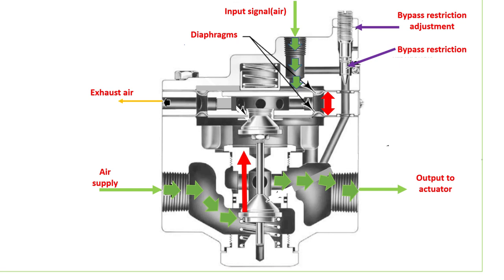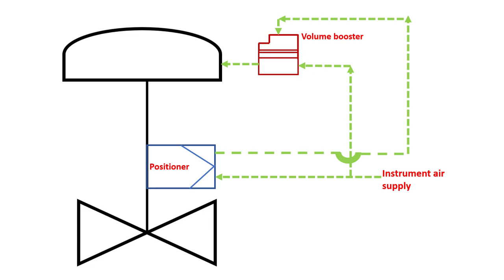We have an input air signal at the top port. This input signal may come from solenoid valves or from positioner output. We also have an air supply input and an output to the actuator. The air supply comes from instrument air, and the other port is the output to the actuator — this is the final volume booster output going into the actuator. We also have a bypass restriction adjustment and an exhaust.